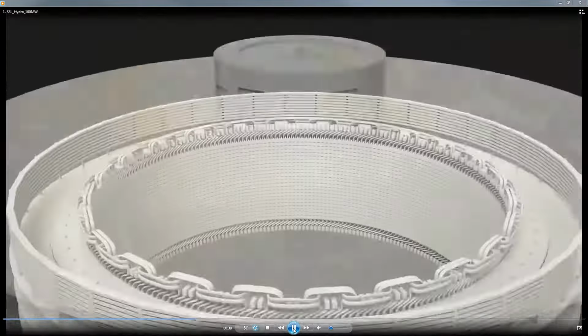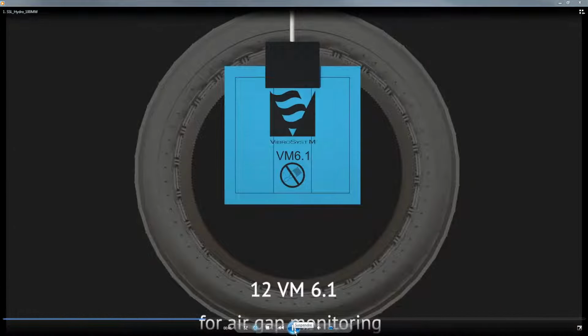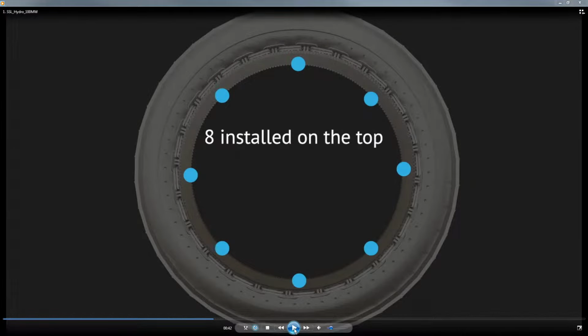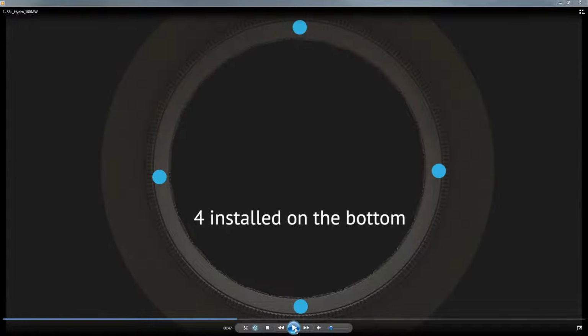Okay, here we have an example of an air gap sensor. This is one type. We have a few different types depending on the gap, depending on the location. We usually recommend 12 in this setup: 8 at the top and 4 at the bottom. I was asked the question, why 4 at the bottom? Well, budgetary concerns are always an issue, of course, and the number of input modules that we have with this system is limited, so we have to make some choices.